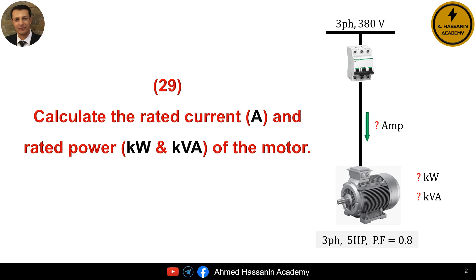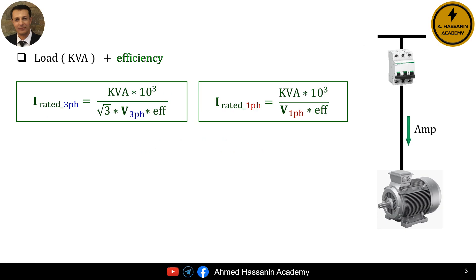Since the motor power is given in horsepower, we must understand an important point. The equations for dynamic loads, such as motors, differ from those for static loads. This means that the equations for dynamic loads include efficiency. Before calculating the rated load current, we first need to know the unit of the load, as there are various units for electrical loads, each requiring a different equation.